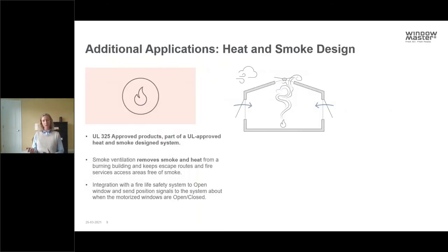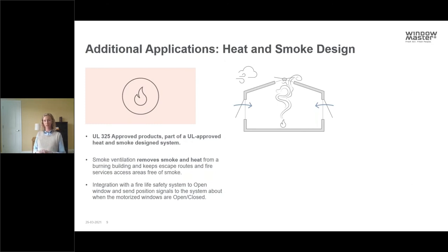Another great application for window actuators, especially in North America, is in a heat and smoke application — using an actuator and control panel as part of a full fire life safety system. Our controllers and actuators would be connected to a notifier system. A lot of our products are UL 325 certified, which means they can be combined with a UL-approved notifying system to allow smoke and heat egress in a project.